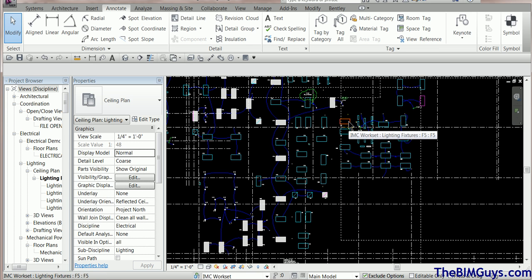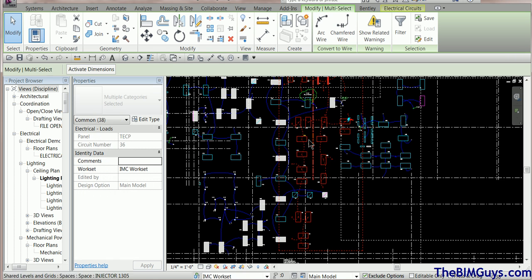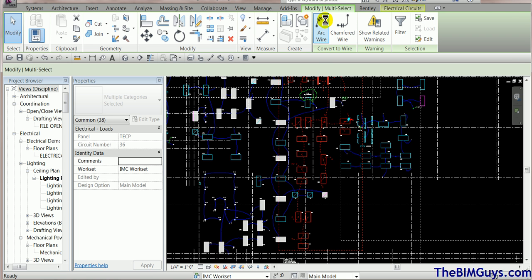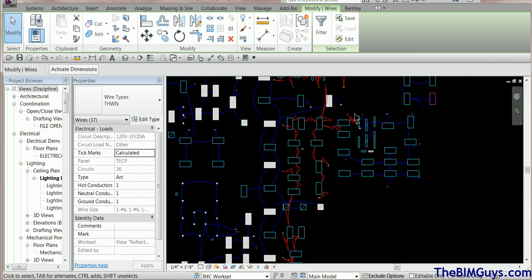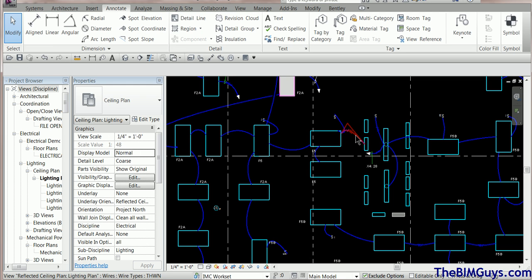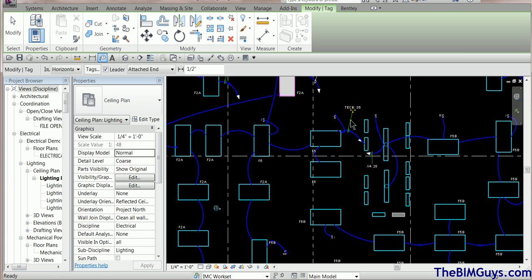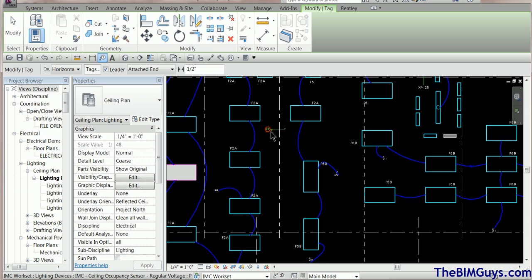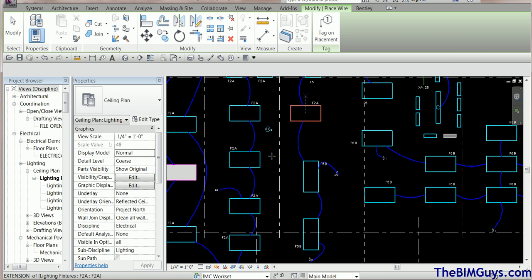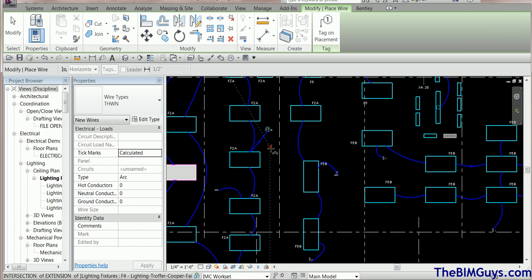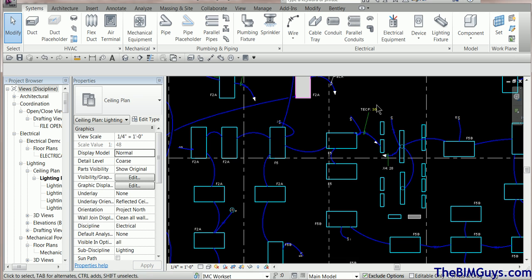Now the wires are all gone — don't panic. Hovering and hitting Tab picks them all up again. Tabbing once more, notice one fixture is being left out — the one we were having problems with earlier. Now I'll wire it all back again. Let's come over and put a tag on here — Tag by Category, touch it — and notice it's happy now. We can then go back and wire that sensor back in via Systems > Wire.